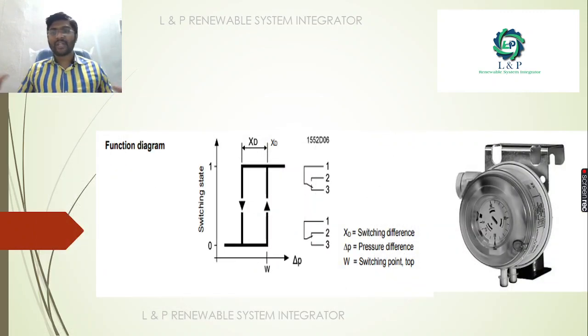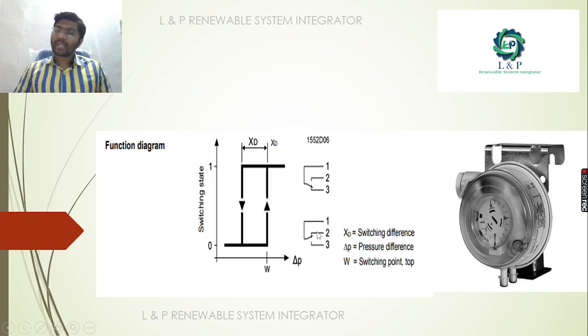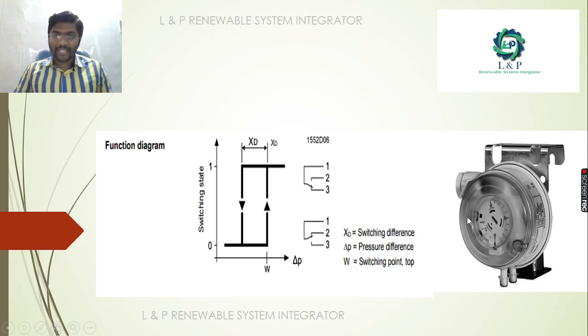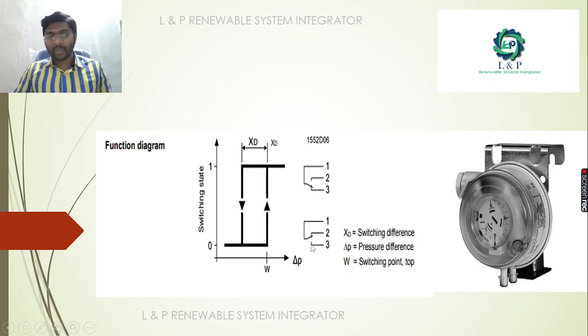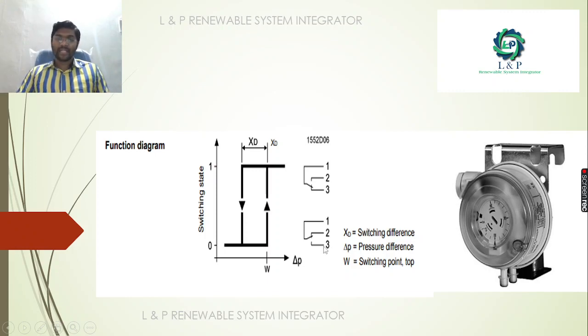In the functioning diagram, terminals 1 and 2 are normally in the NC position. Whenever a pressure change occurs based on the set point, it immediately changes position to terminal 3. So, just like a switch, the NC contact changes to NO, and the terminal that was already in the NO position changes to NC.